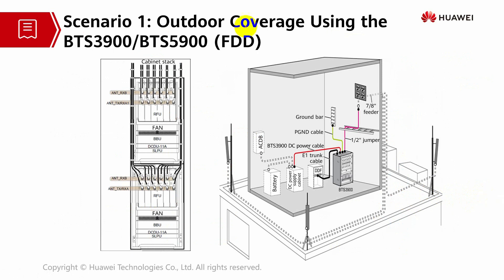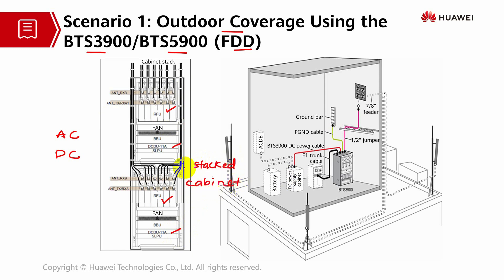Scenario 1 is outdoor coverage using BTS 3900 series or BTS 5900 series in an FDD network. The external power input can be AC or DC. It is configured with RFUs and RRUs. A DC DU with circuit breakers supplies power to the BBUs and RRUs. The cabinets are stacked. The maximum configuration is two BBUs with DC DUs and around nine RRUs giving less than 800 watts total power consumption, compared to six RRUs which can give up to 1200 watts.